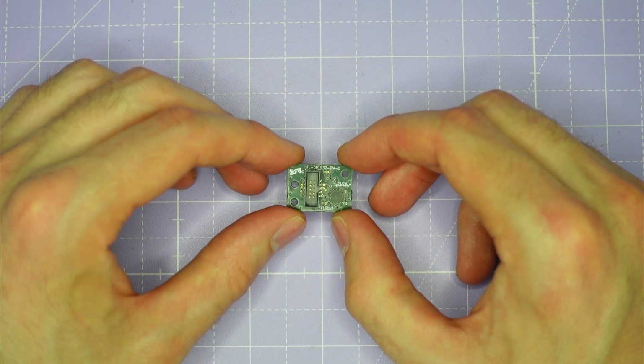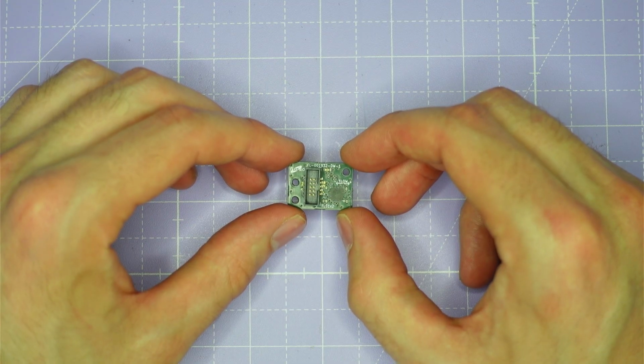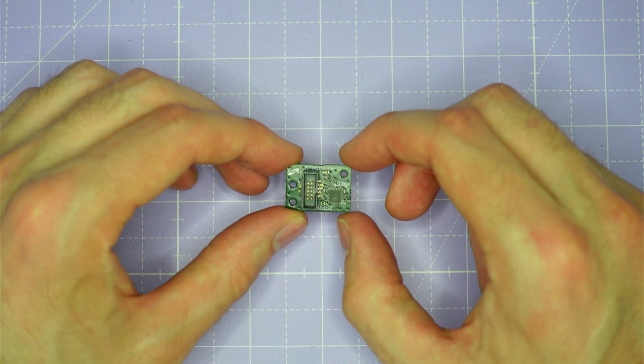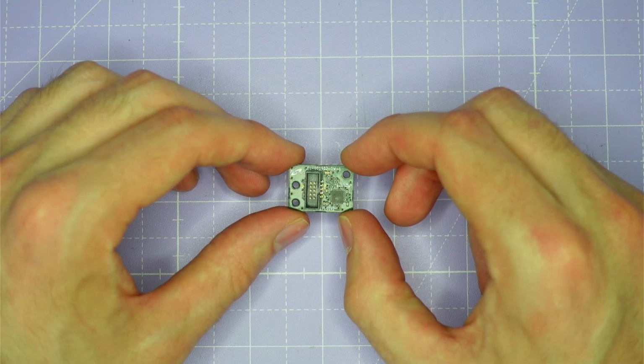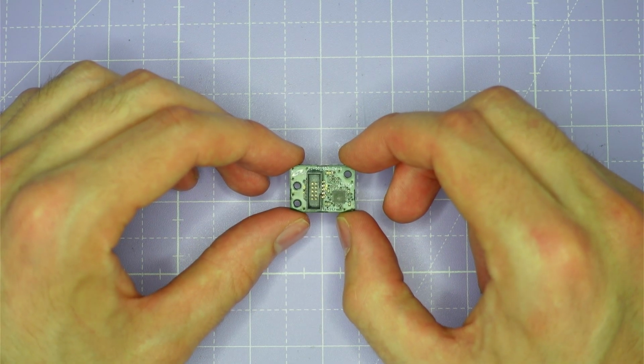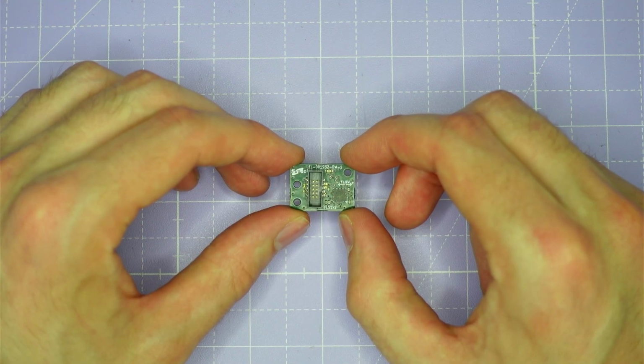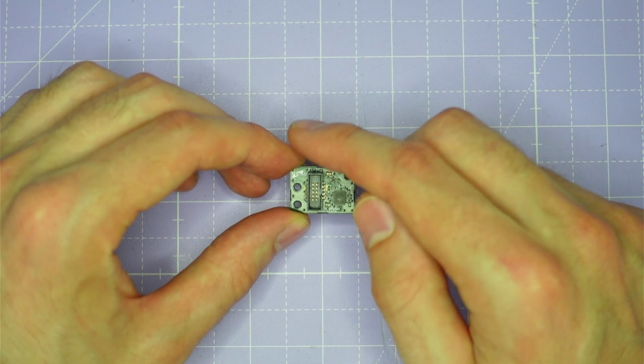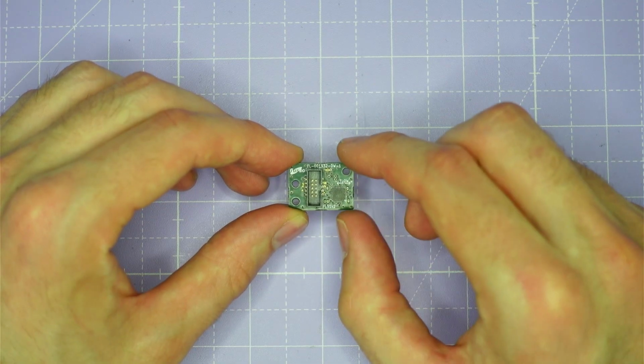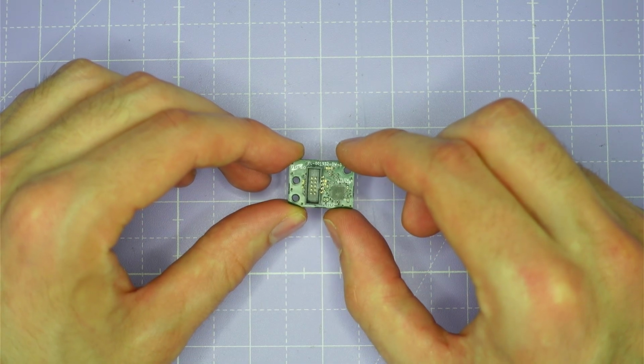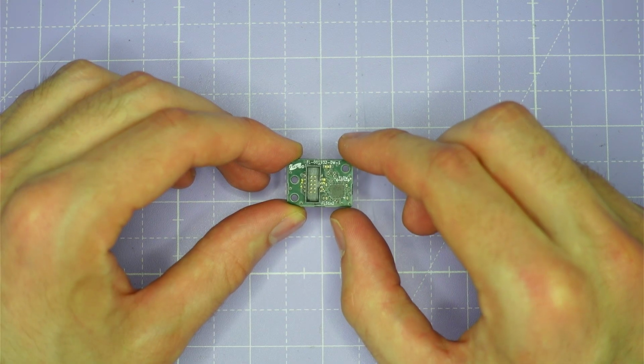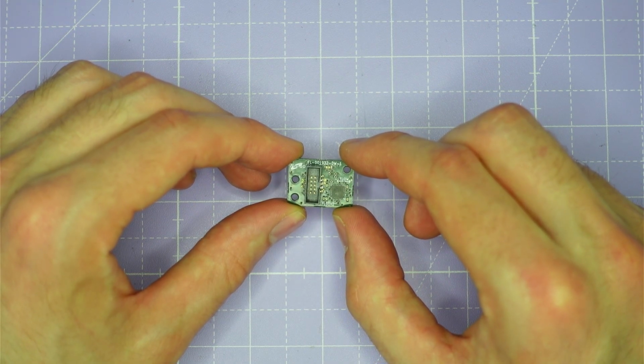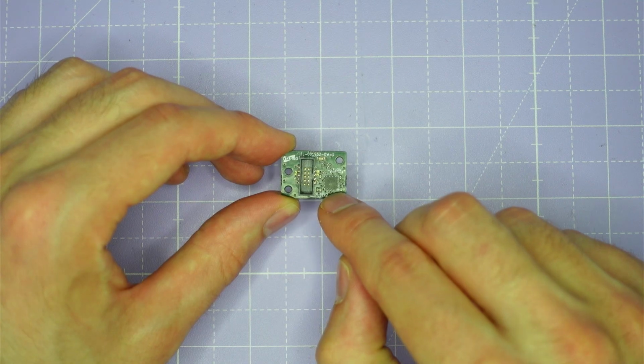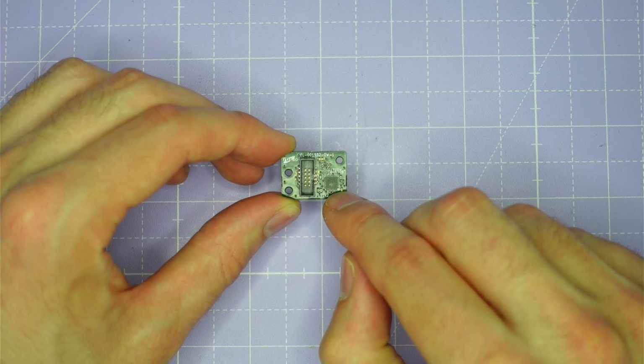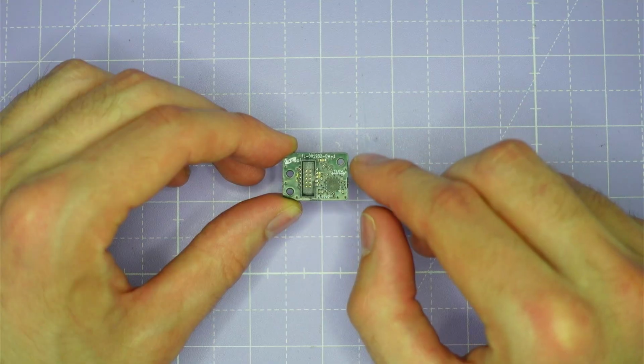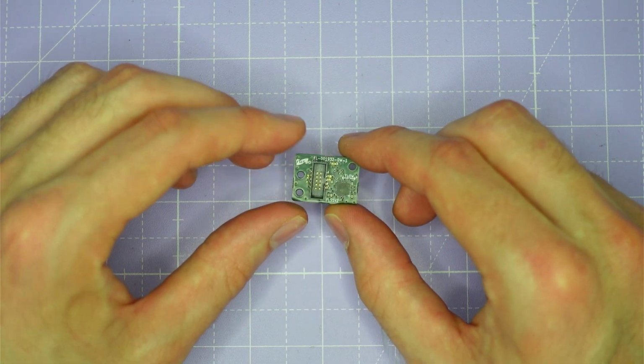I'd like to start by showing you the Flusso FSE-112 flow sensor module. As you can see, this module is a small PCB, 16 by 22 millimeters, and it's able to measure mass flow, volumetric flow, and differential pressure in both the positive and negative flow directions. On this side of the board, you can see the connector for the module, which is a 2 by 5 way box header connector with a 1.27 millimeter pitch. And there's also this microcontroller here, which drives and reads the flow sensor on the other side of the board to provide the flow readings over that digital I2C interface.